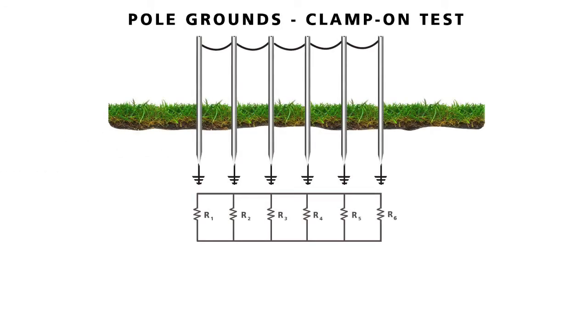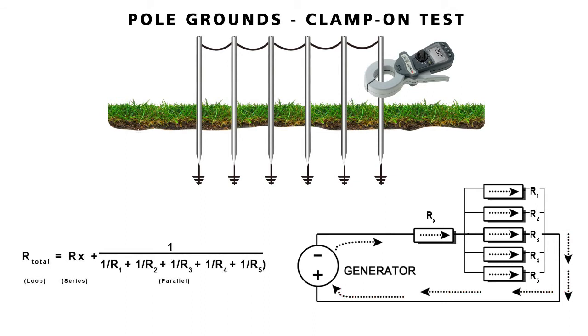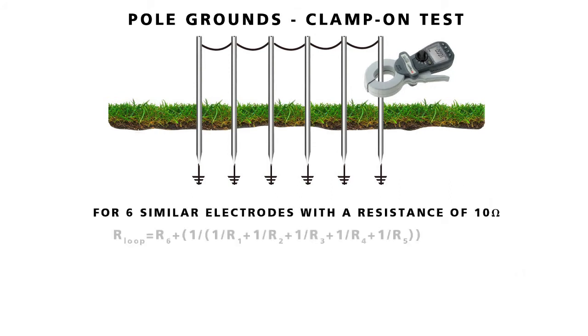Imagine a string of pole grounds paralleled together through a grounded system neutral, each with a 10 ohm resistance. The clamped rod becomes a resistance in series with the combined parallel resistance of all the other rods. The remaining rods in system neutral provide the return path. The measurement is the resistance of the rod under test plus the elements of the return path. The return elements add to the reading and therefore contribute an error.